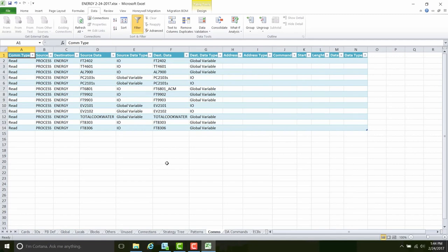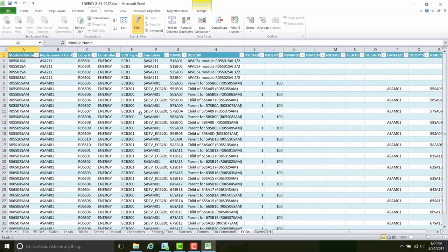After that is a tab for communication coming and going from a controller to another system. This could be a third-party device like a PLC or specialty measurements. Whatever the system is, you'll see that the communication is occurring. Let's look at the hardware configuration tab, which captures all the input-output modules and creates equivalent hardware. We capture the failsafe feature of all points and reapply the same failsafe in our system. We automatically create full system configurations, which will be used in I/O point generation.